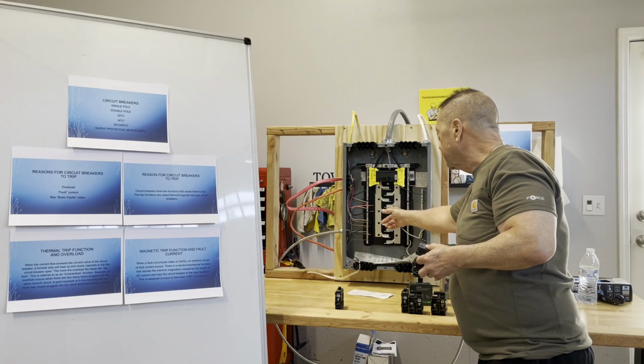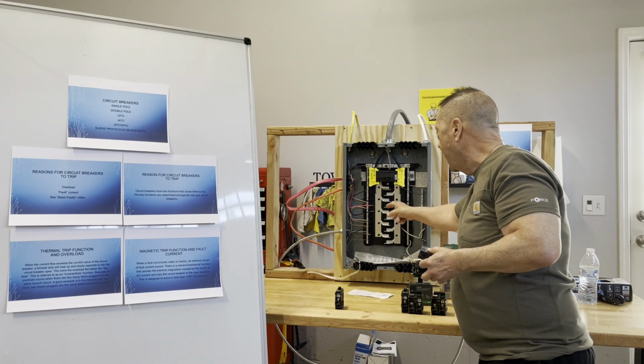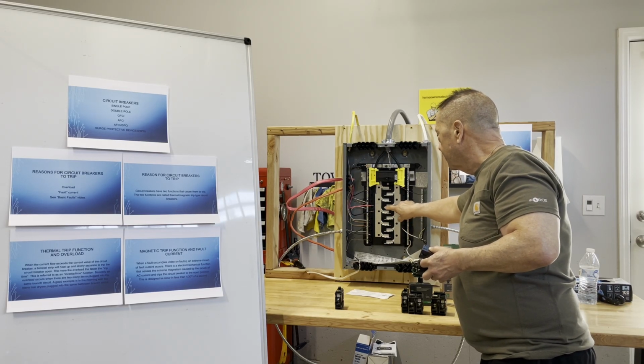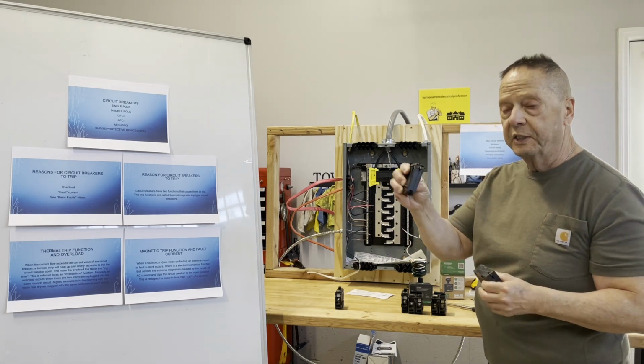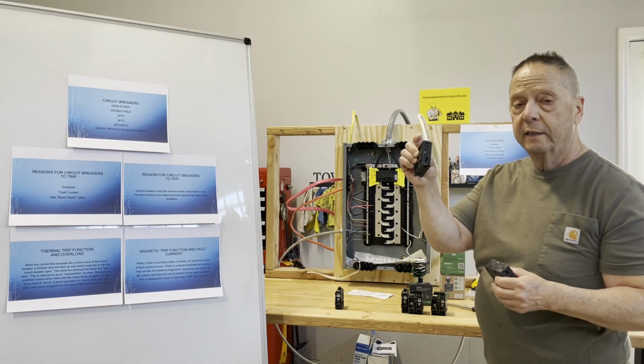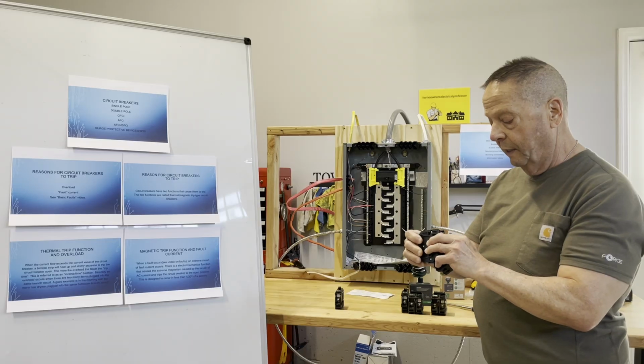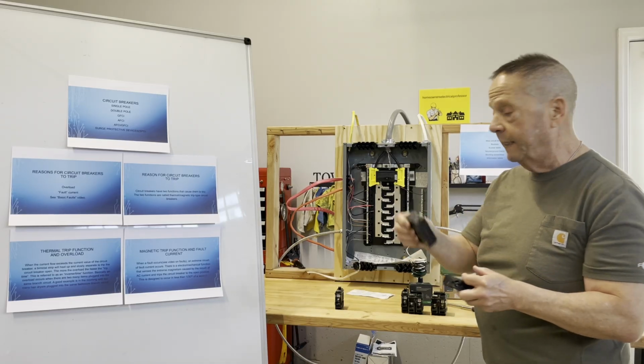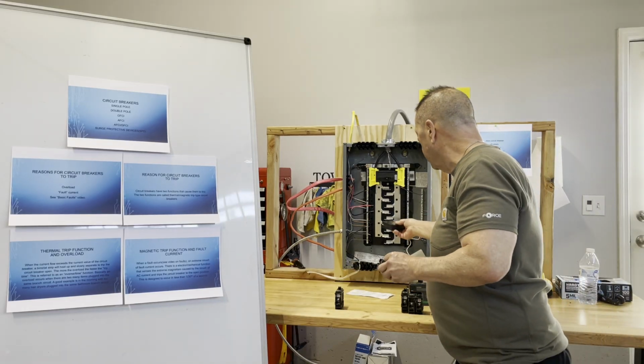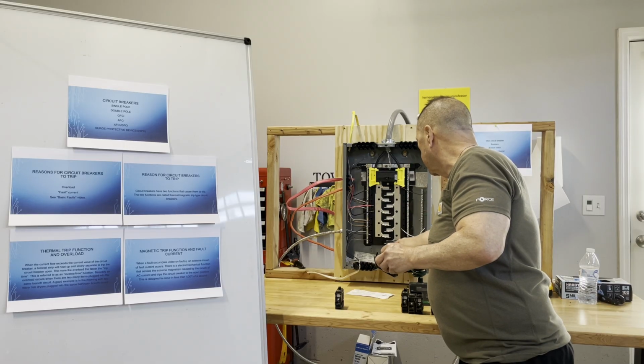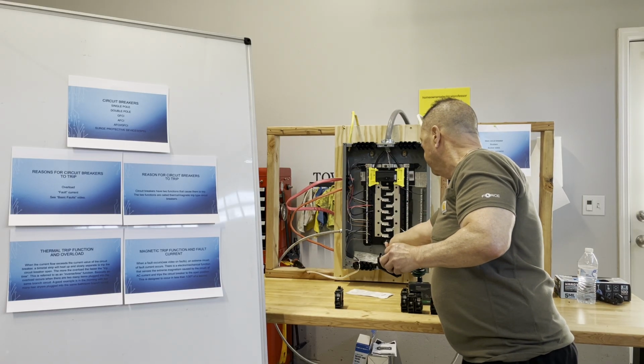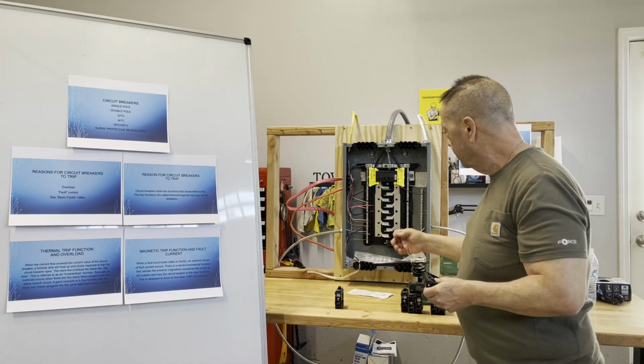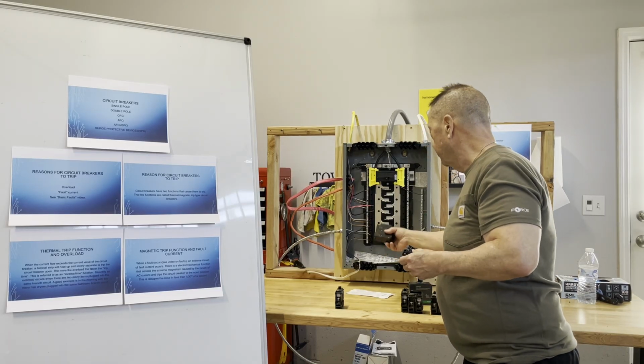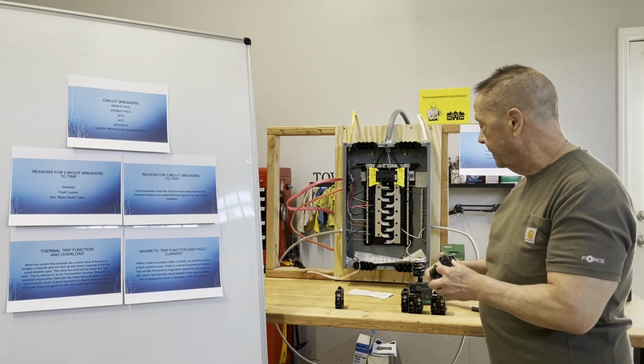If the bus bar stabs have this notch, if this is flat across here, your panel is not designed to take the tandem circuit breaker, and it will not fit in there, okay? This panel is designed for them, so the circuit breaker will fit in there, okay? So be careful of that. If your circuit breaker is older and isn't made for that.